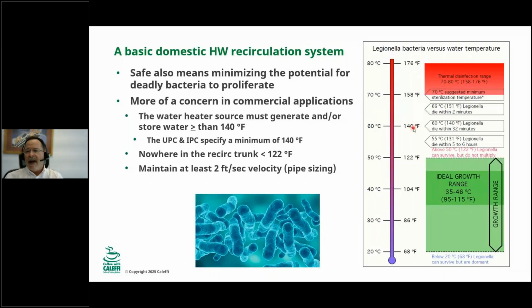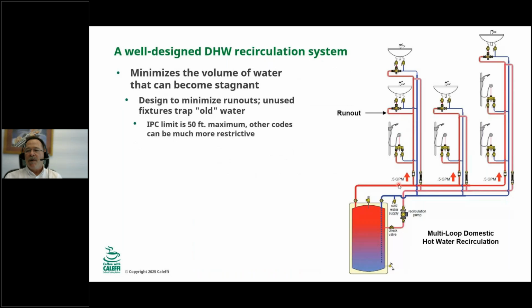Here's a slightly different graph, similar but different. Now this one is a multi-loop domestic recirc loop, and you can see that the hot water trunk is the same, but now we have, I'll call these risers or secondary circuits or takeoffs, whatever term you might use where you work. But in terms of designing a system like this, the designers want to minimize fixture runouts. So a fixture runout is anywhere from the hot water source to the fixture. Now in this case, in this schematic here, the hot water source is this riser hot water pipe right here. So the runout is this piece right here.